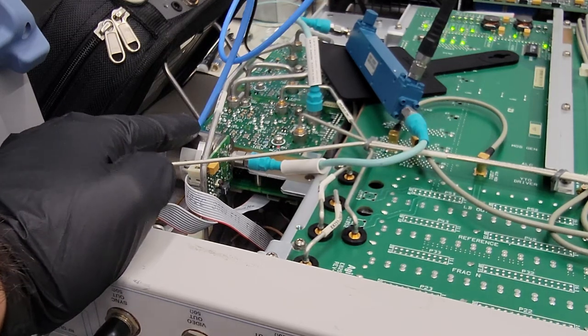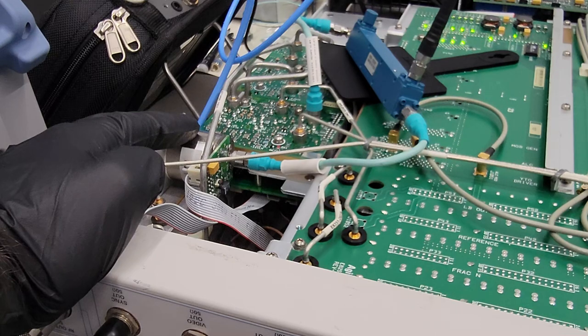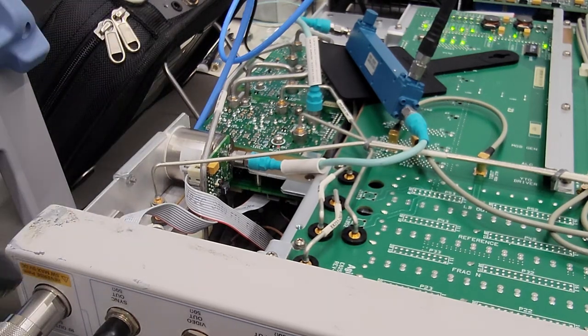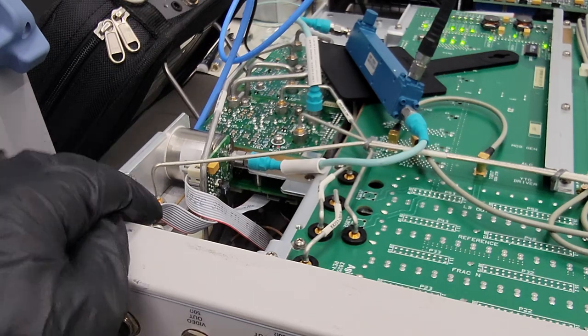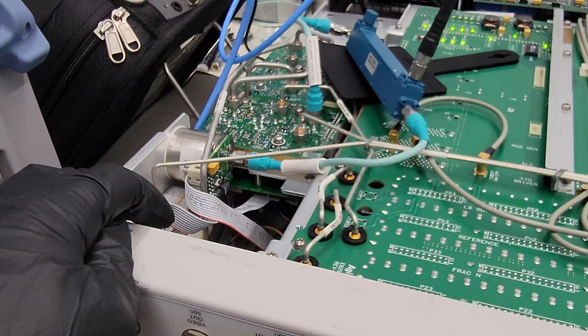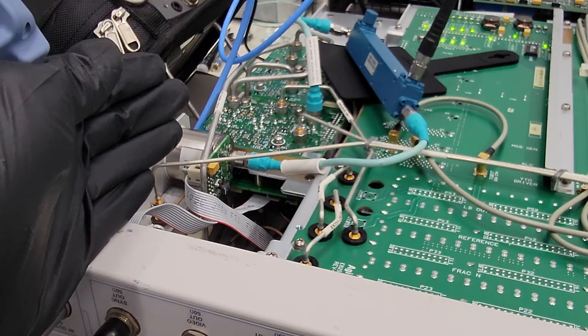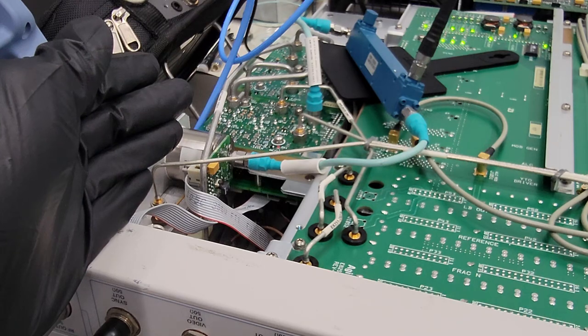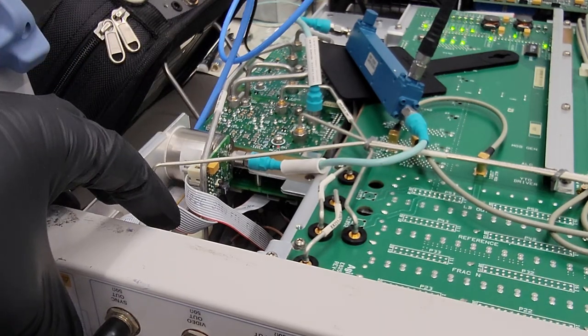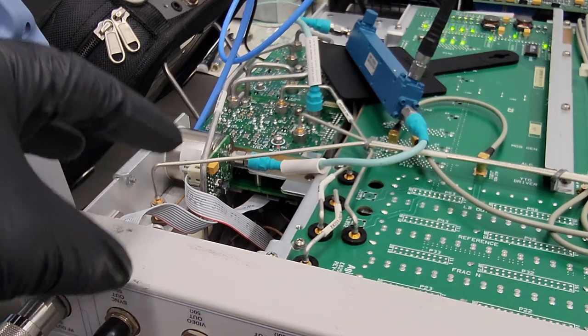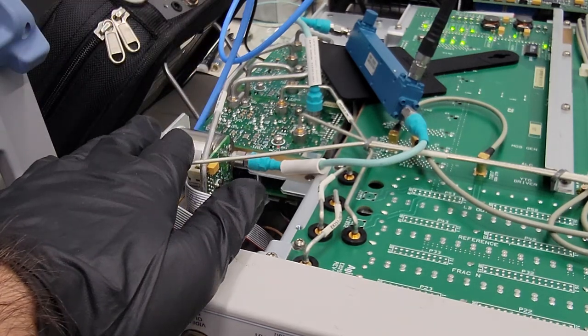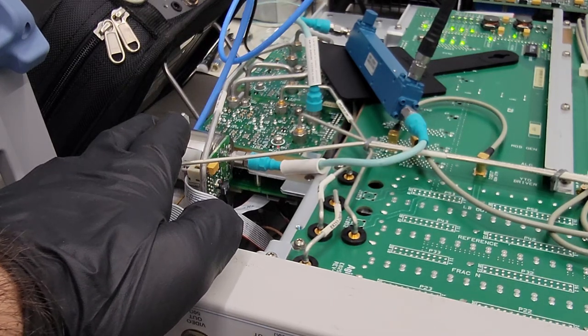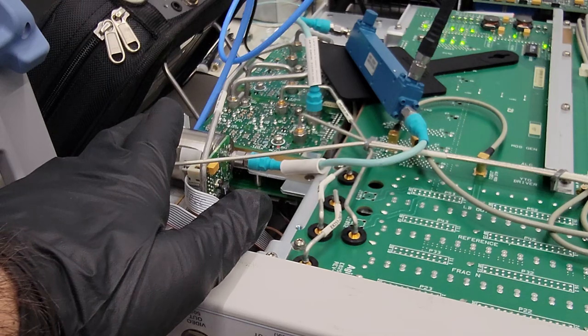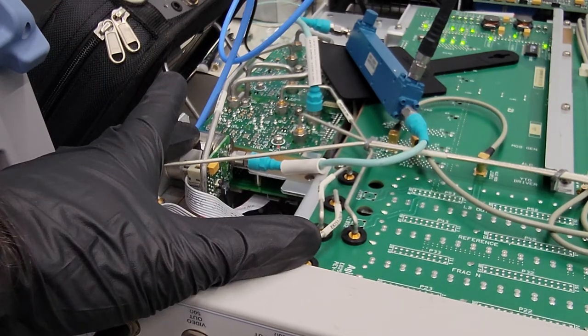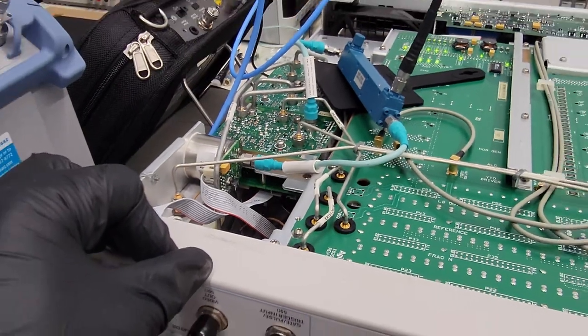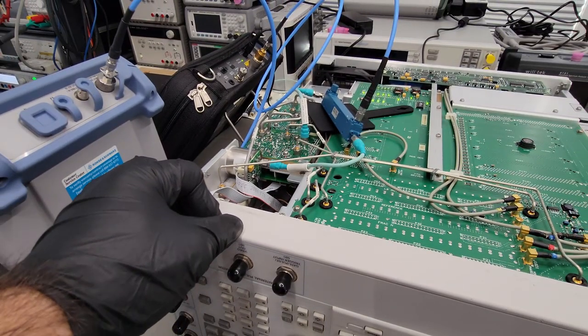And I think in order to go systematically and try to debunk where this low amplitude issue is coming from, because we've already ruled out the possibility of the output connector and the attenuator being problems, because we measured directly at the output high band directional coupler and we saw that the signal was indeed low there. So we know that these few mechanical components largely in the front end are not responsible for that. We probably have an electrical issue. We're losing gain somewhere in the signal path. So we can start by tracing where the signal begins and try to isolate the block in the instrument where we have that low gain, and then we can investigate further at a component level.